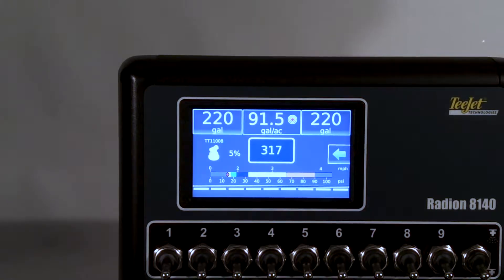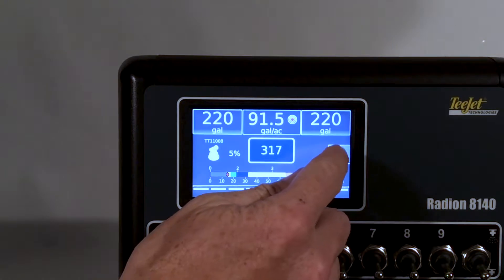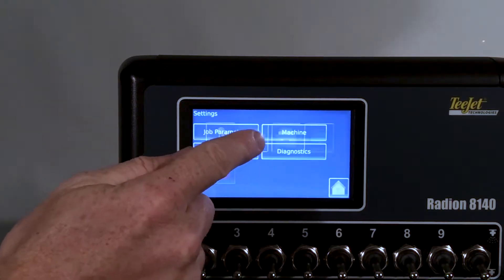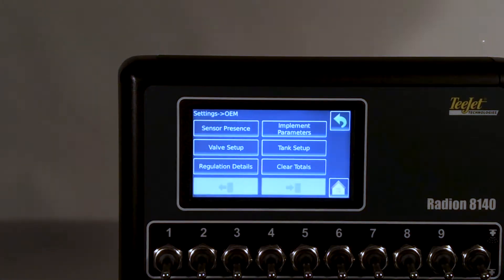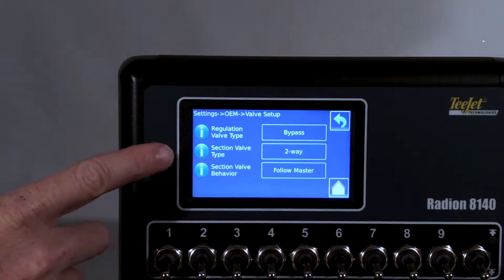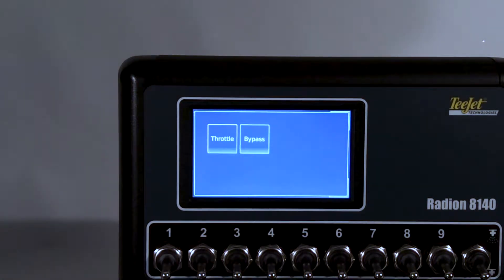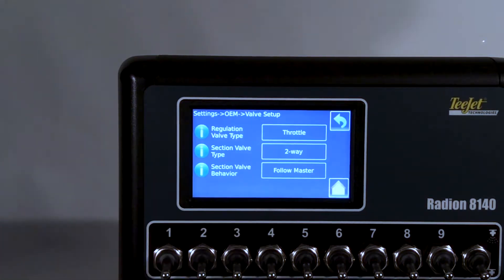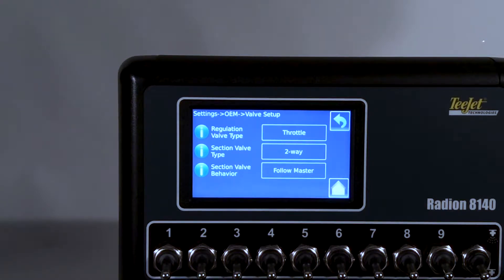Regulating valve position. This can be found by exiting the work mode with master off, then navigating to Home > Setup > OEM. The OEM password is 9090. Enter Valve Setup, then enter Regulation Valve Type. There are two choices: bypass or throttle. Bypass means the regulating valve is in the return line back to tank. Throttle means the regulating valve is in the main flow line.